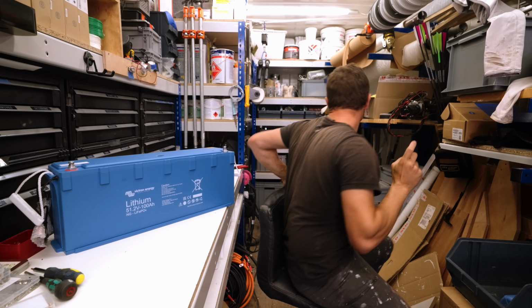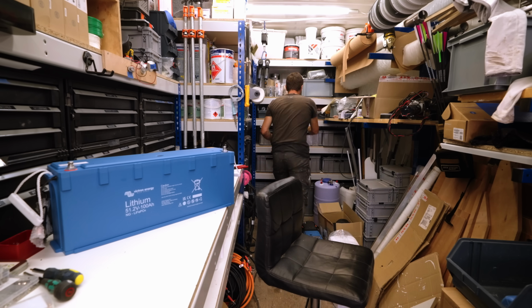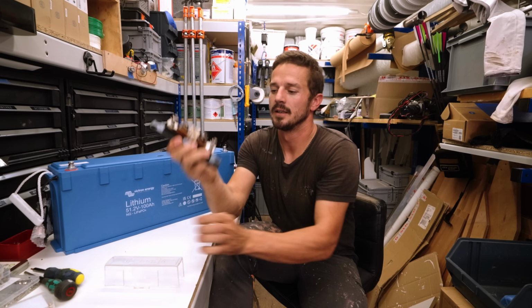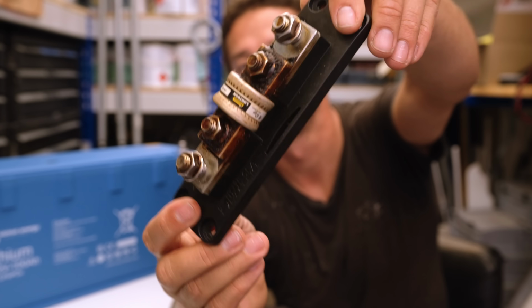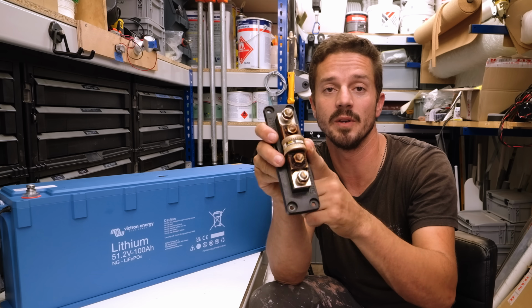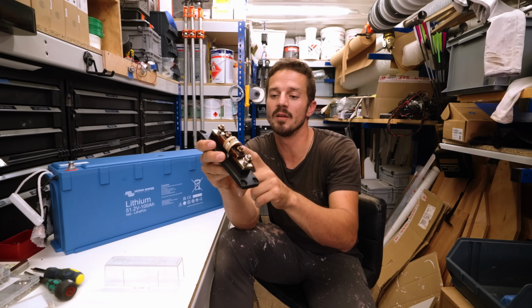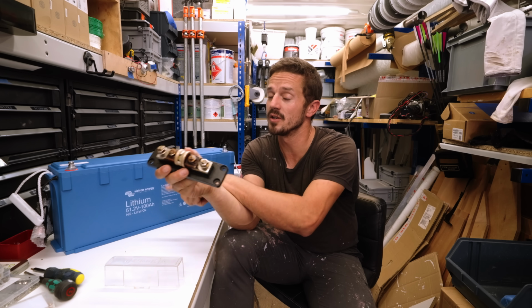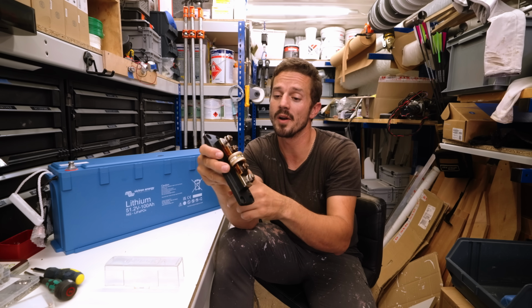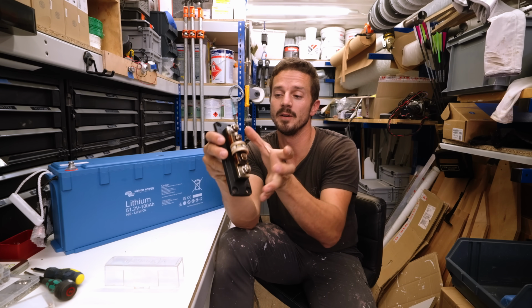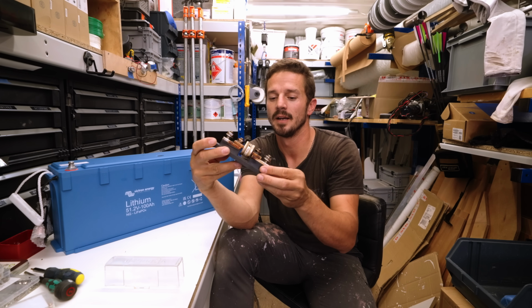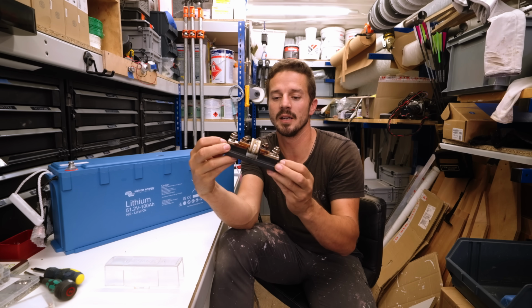What we had before was this - a marine grade Class T fuse holder with a Class T fuse. This one is 400 amps, and it's what we used to run our whole boat off of. We don't need a full 400 amp fuse on each battery - we could probably get away with 100 or 150 - but the fuse holder is the same size regardless, and it's a big chunky thing.